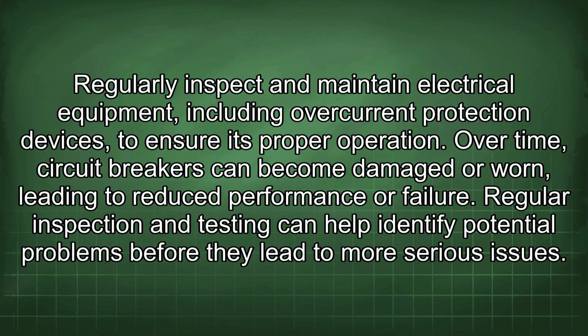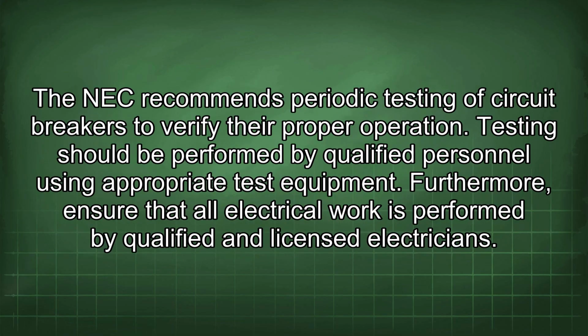Regularly inspect and maintain electrical equipment, including overcurrent protection devices, to ensure its proper operation. Over time, circuit breakers can become damaged or worn, leading to reduced performance or failure. Regular inspection and testing can help identify potential problems before they lead to more serious issues. The NEC recommends periodic testing of circuit breakers to verify their proper operation. Testing should be performed by qualified personnel using appropriate test equipment.